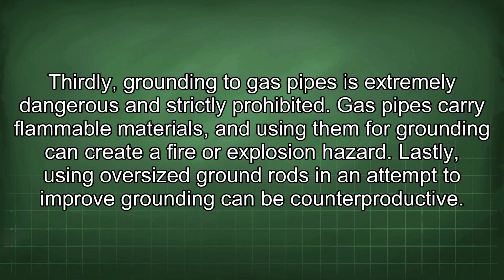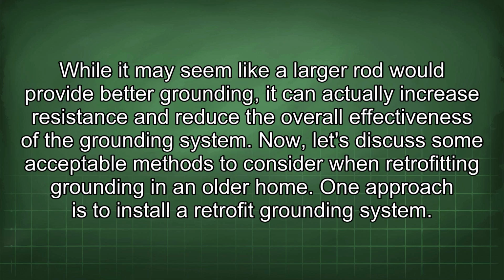Lastly, using oversized ground rods in an attempt to improve grounding can be counterproductive. While it may seem like a larger rod would provide better grounding, it can actually increase resistance and reduce the overall effectiveness of the grounding system.